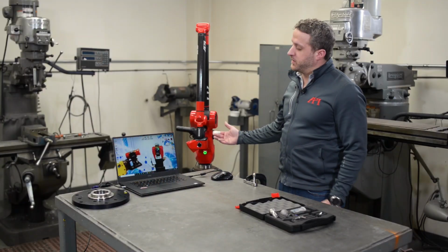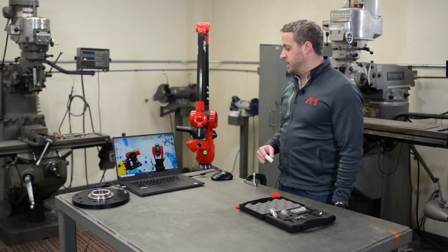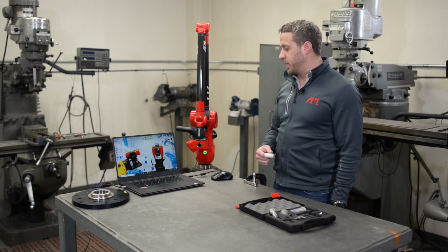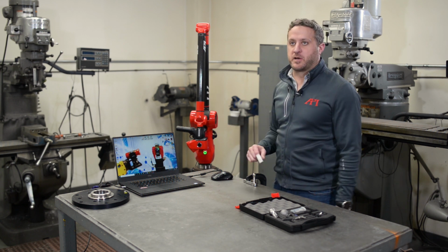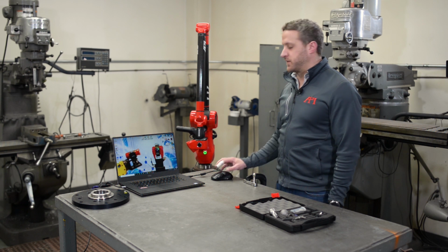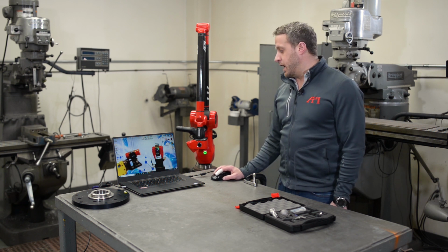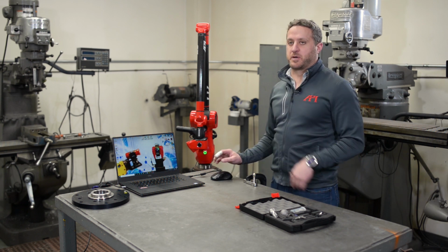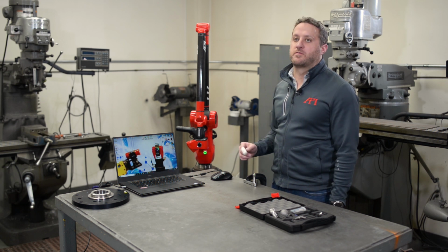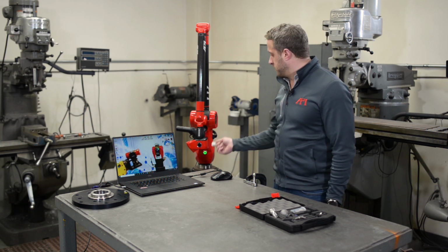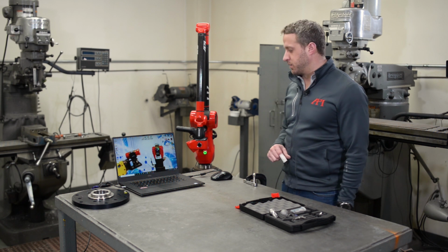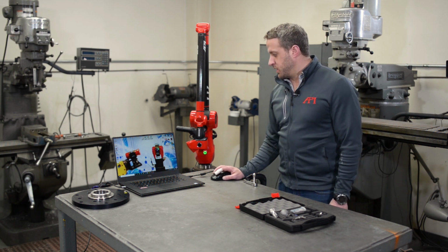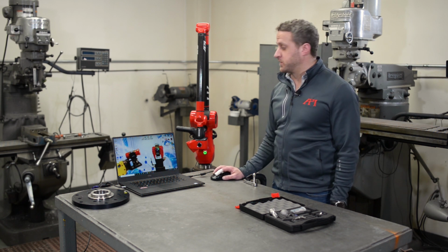So again, the arm is connected through the Ethernet port. During the installation process, the drivers will configure your Ethernet adapter to connect automatically. So I'm actually gonna go through the calibration process in the third-party software, and then I will install the probe on it and we'll go through a calibration with that. So for this sake, I'm gonna be using Verisurf.